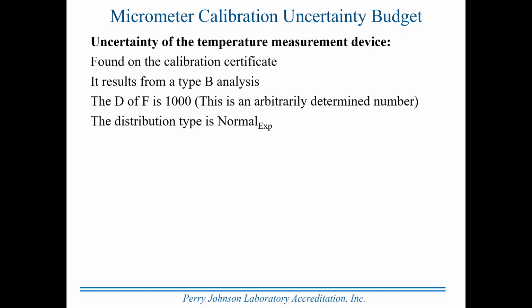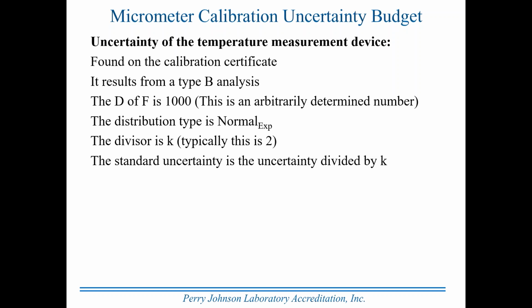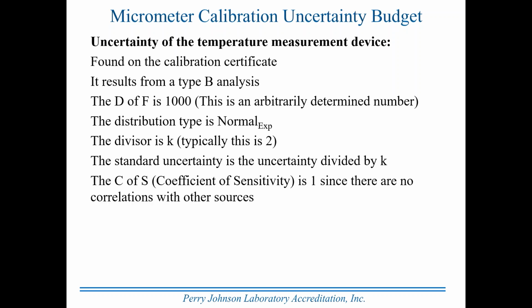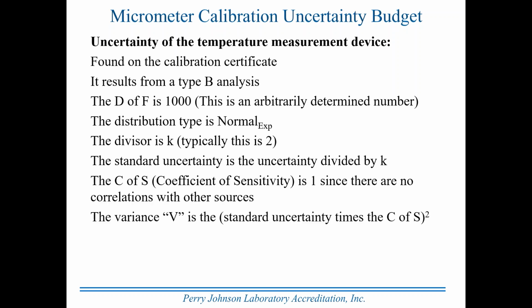The distribution type is normal expanded, which means the standard uncertainty or standard deviation of the distribution was multiplied by the coverage factor, which in this case is 2. Standard uncertainty is the uncertainty divided by K. Coefficient of sensitivity is 1, no correlations. Variance calculated in the same manner.